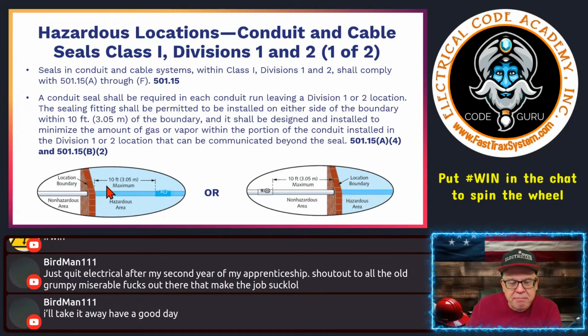Personally, my preference would be to have the seal in the hazardous area, because typically you're not going to have any type of coupling inside of the transition. This might be a rated assembly, so I have to be careful of it penetrating through. In this case, I'd rather it be over here because it's not going to allow any communication through this portion of the wiring method. Whereas out here, if there's an issue, it would allow some of it to get outside of the boundary. But that's just a preference.